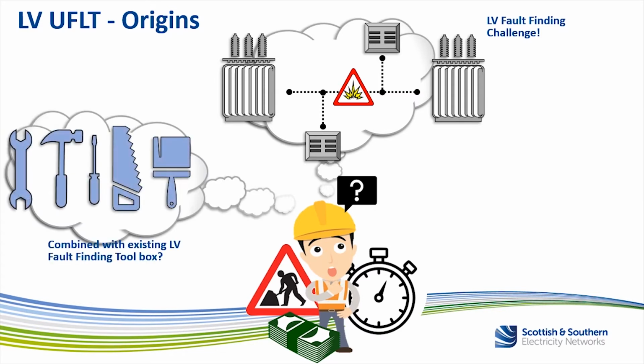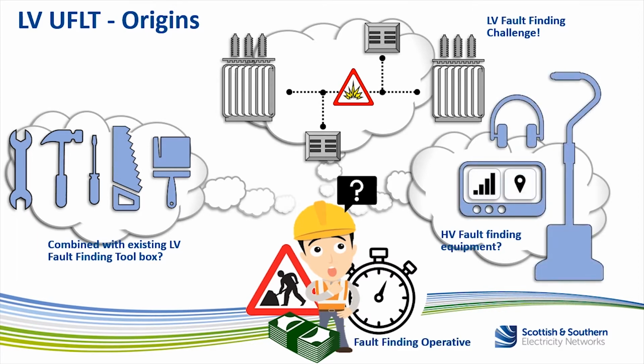Scottish and Southern Electricity Networks has, over the years, been building the toolbox the operative has ready when going out to find that fault. We've looked at the thermal imaging camera, which utilises the heat given off by the fault. We've also utilised the cable sniffer, which uses smell, and the HASIS device, for phase identification. All these tools are in the operative's toolbox to help them. But the one thing we hadn't looked at, which LV UFLT was to utilise, is acoustic. We were aware of acoustic fault finding equipment on the HV network, and part of the project was bringing that acoustic technology onto our LV network, while incorporating all our existing work within the business. The outcomes are on the next slide.